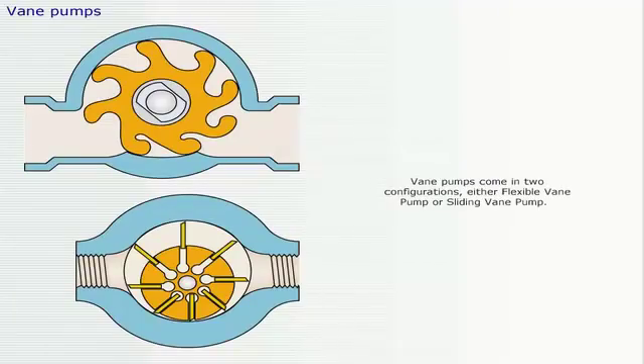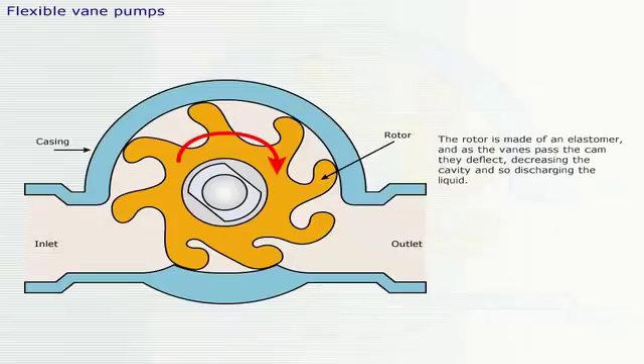Vane pumps come in two configurations, either flexible vane pump or sliding vane pump. The rotor is made of an elastomer, and as the vanes pass the cam, they deflect, decreasing the cavity and so discharging the liquid.